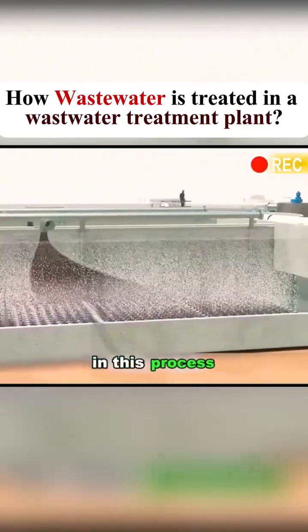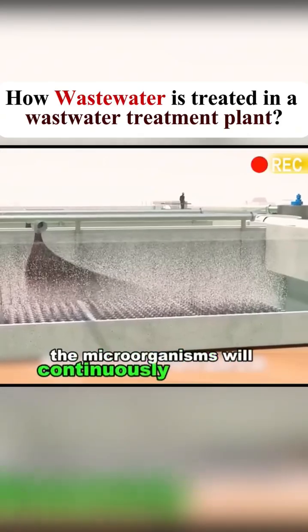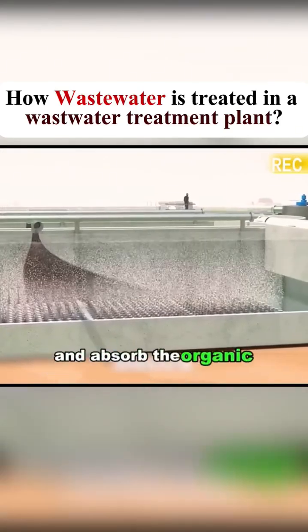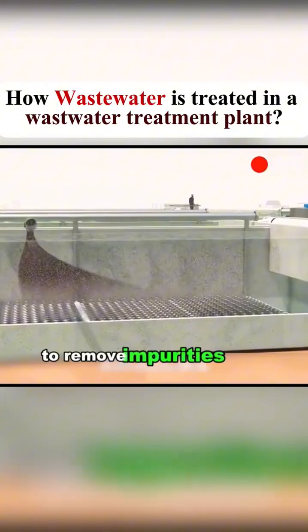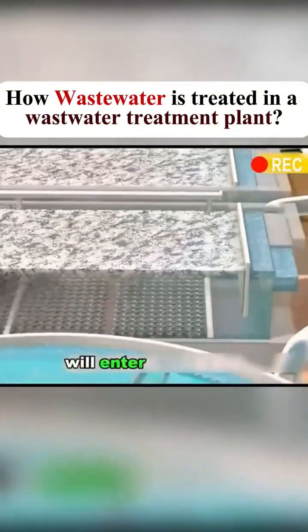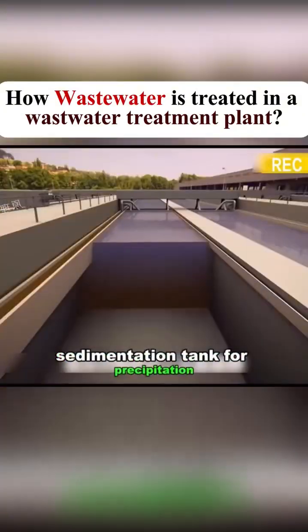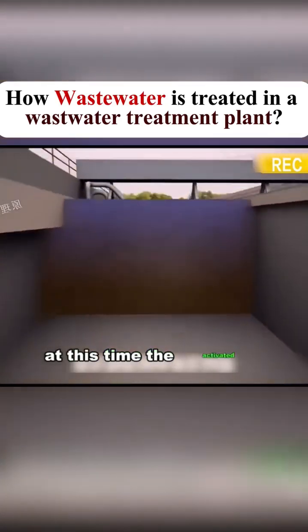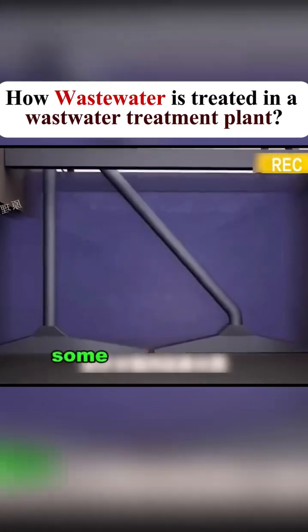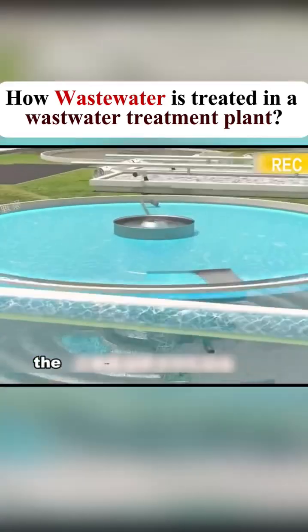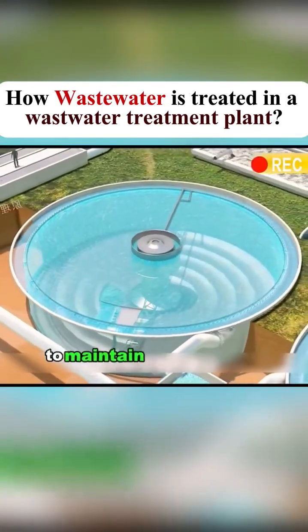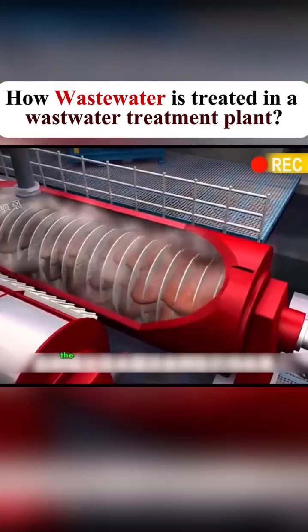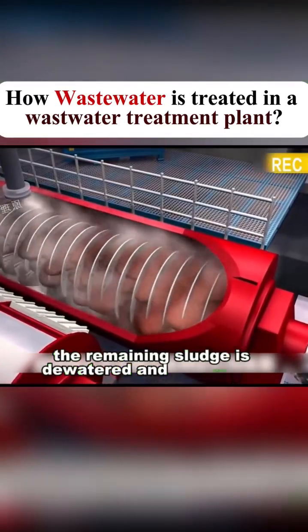In this process, the microorganisms will continuously decompose and absorb the organic matter to remove impurities. After the treatment, the sewage will enter the secondary sedimentation tank for precipitation. At this time, the activated sludge in the sewage will be completely separated from the water. Some of the separated sludge is returned to the biological treatment unit to maintain the microbial concentration. The remaining sludge is dewatered and discharged.